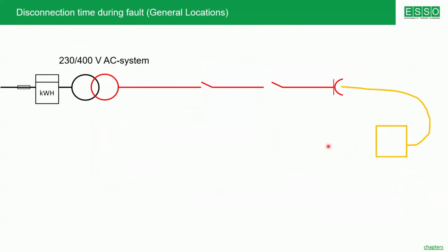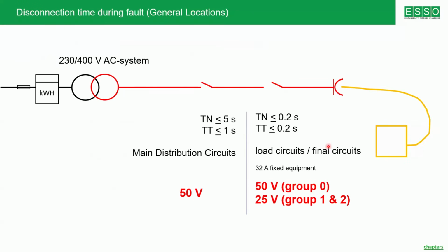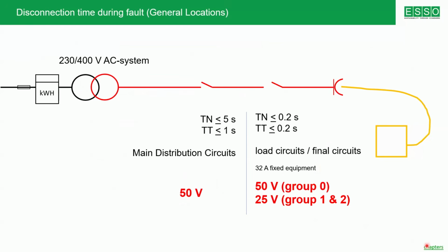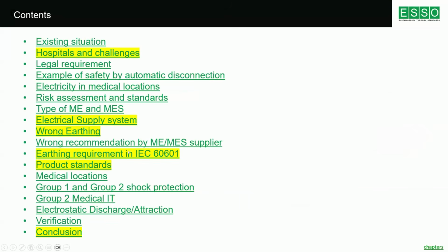The subject of earthing, as I am explaining one by one, is a different subject. It talks about disconnection time. It talks about the touch voltages. Here in the picture, what you are seeing is you have a 230-400 volt system. You have the high voltage side, you have the low voltage side. For the fixed installation, main distribution circuits 50 volt, and for the group 0 location 50 volt, group 1 and group 2 locations 25 volt. These are the maximum allowed touch voltages in these locations. So now, coming back to the subject, there are requirements for the medical electrical equipment. There are requirements for the supply system.